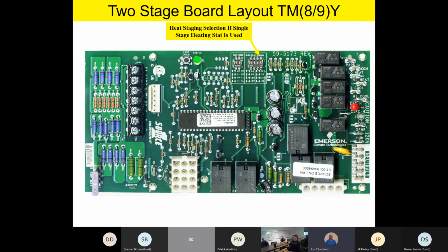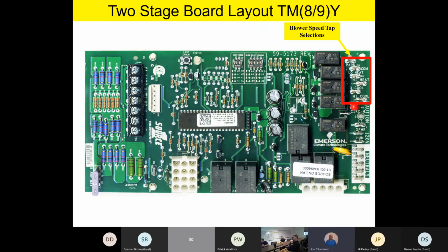Okay, well, let's go ahead and work around the board then. As we come over to the right-hand side of the board, we have some blower speed tap selections. This is where you're actually going to select your speed taps for low heat and high heat, low cool and high cool if you have a two-stage piece of equipment outside. And so this is pretty straightforward.